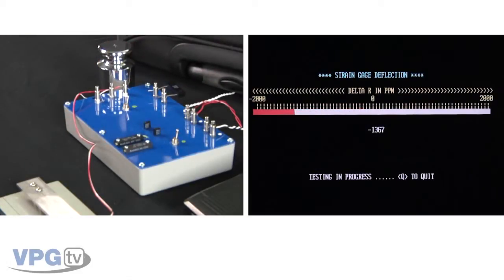Exactly negative 1,367 ppm. The same as the 1,000 gram weight standard. The same procedure also works on a much larger scale for extremely heavy weights where moving them around is difficult and impractical.